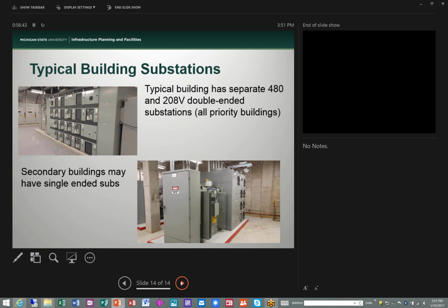Getting back to an earlier question about your feeders and their sizes, I know how systems evolve over time. What is your longest feeder? I'll mention this in the context of running power from our central heating plant back in the early 60s to the athletic campus. We started at 350 or 500, then stepped down to 350, and successively smaller, so that by the time you got to Chrysler Arena, the better part of 2 miles away - I measured it at 1.7 miles in its normal configuration - we had considerably smaller feeders. So what is the longest length of any leg of your primary selective system?